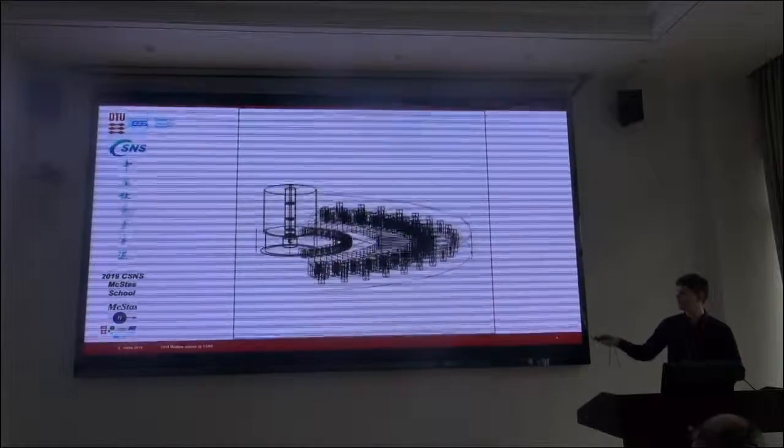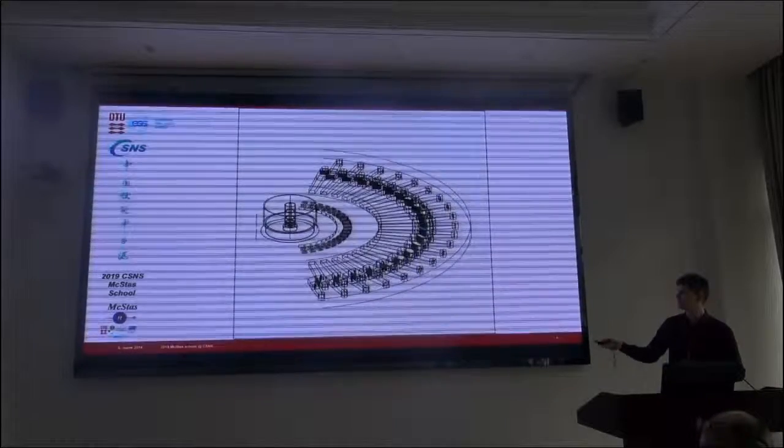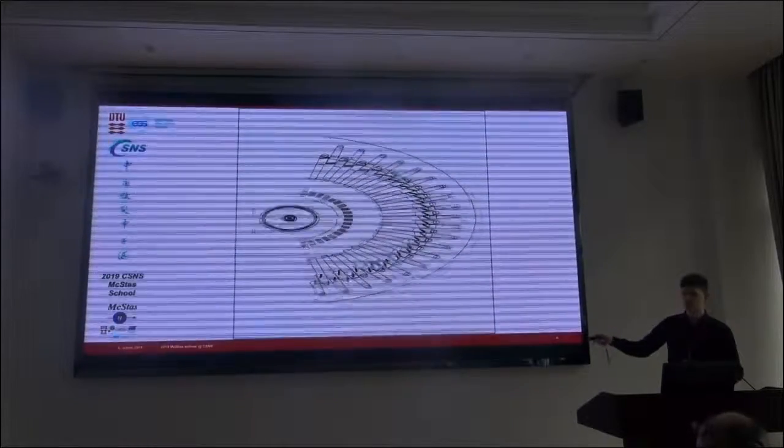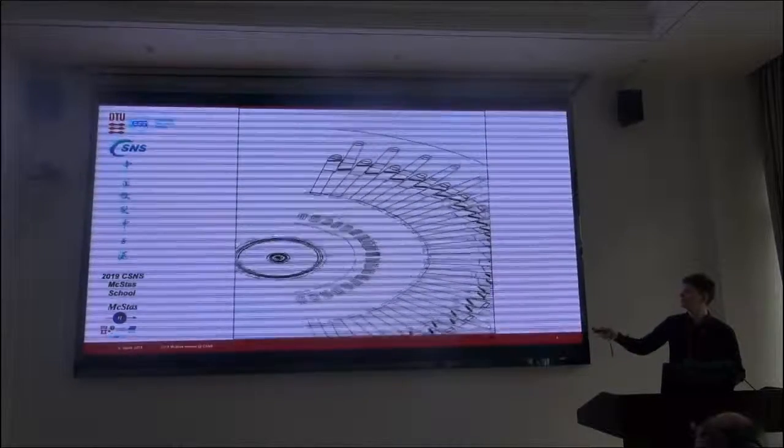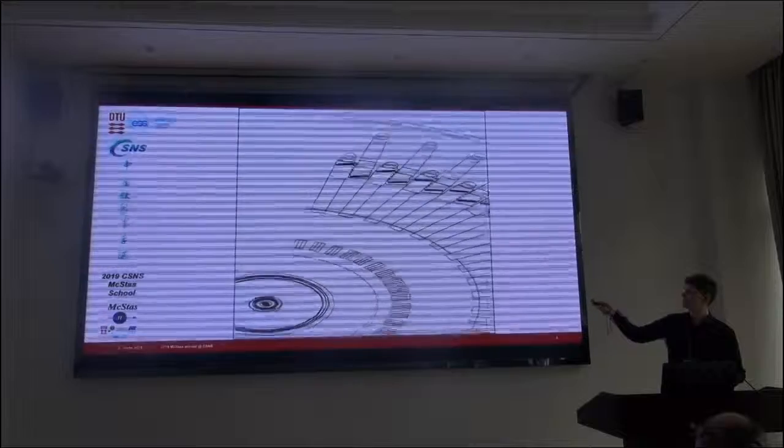As I said, it's 20 channels with shielding in between, and they have two analyzers. They are set for different energies here so that the beam continues in the same direction.